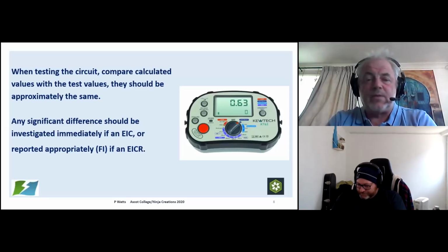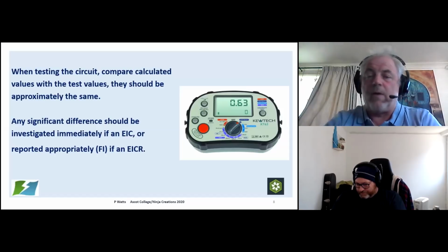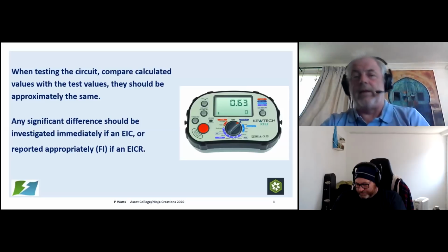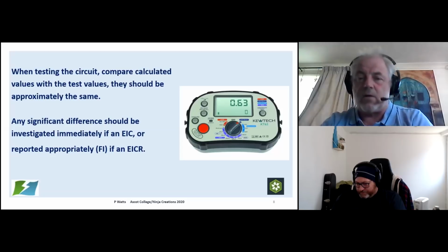Right? Because sometimes you get a reading and you think, what on earth is that about? And you don't understand it. Okay, you have to put down further investigation on that one. You haven't got the time to. You could spend a day looking for why. You haven't quoted for that within your EICR cost.